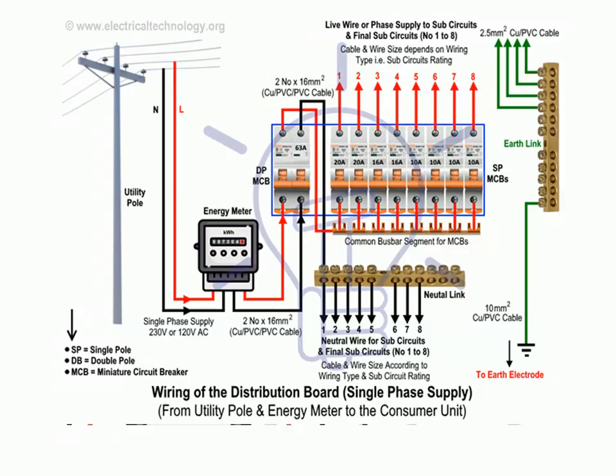Whenever an overload condition or short circuit condition occurs, if you assume the load is 10 ampere, we are using a 10 ampere MCB, then the MCB remains on. Whenever it crosses above 10 ampere, for example, if you are passing 12 ampere or 15 ampere, then the MCB goes off. Just like a fuse blowing out, here the MCB becomes off. Hence, it protects the electrical equipment of the house from the main supply. This is the main thing. It is also called your meter board or distribution board. Later on we can refer to it as a panel board. It is a simple arrangement. It consists of the energy meter. It consists of the MCB. In earlier days a fuse was used.